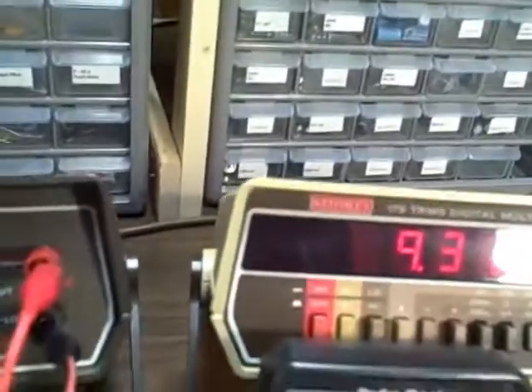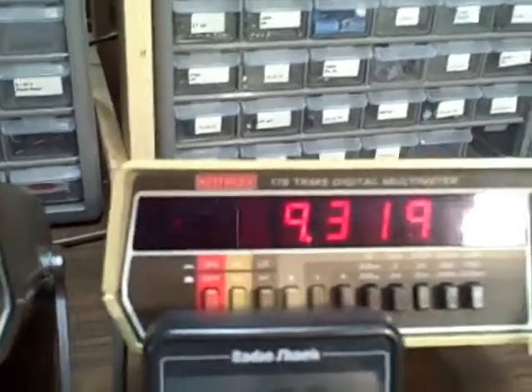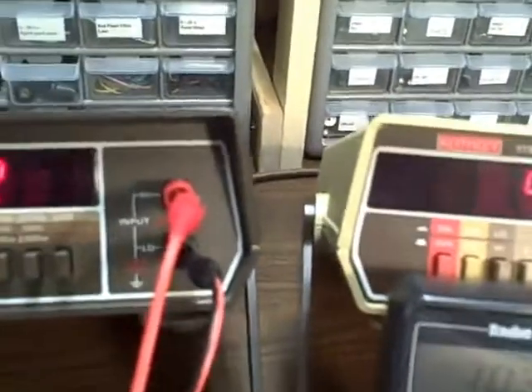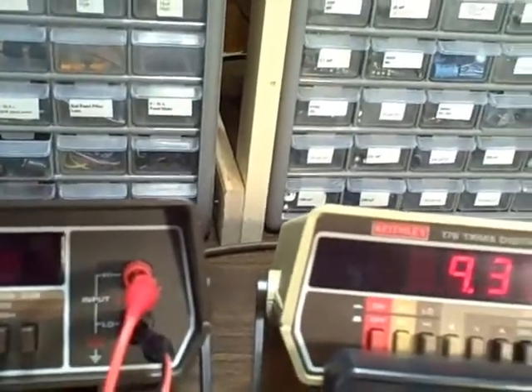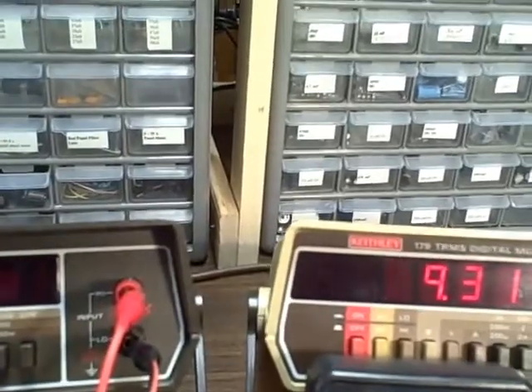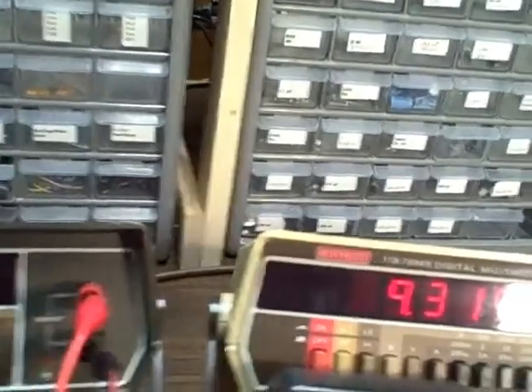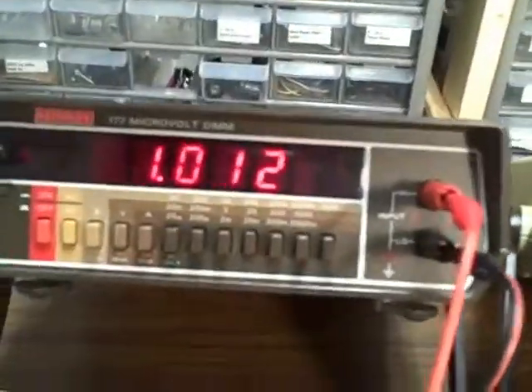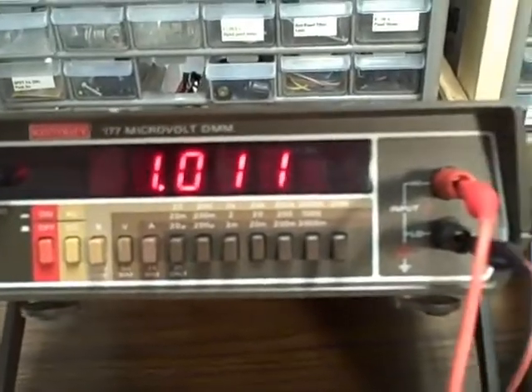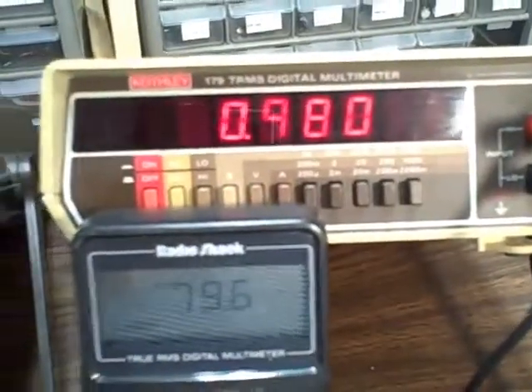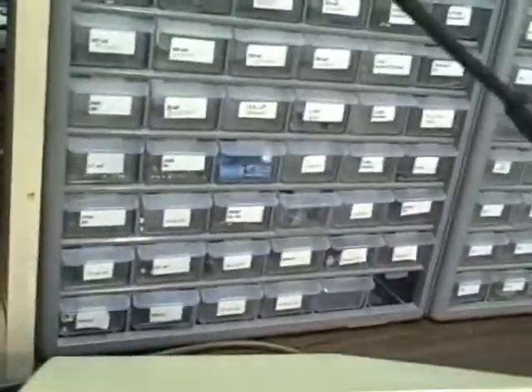But at any rate, the two Keithleys are within a third of a volt at this voltage level, and it is 10 times higher in range than it's actually meant to do. I'm going to go ahead and turn down the voltage. We are reading 1.012 on the 177 and 0.980 on the 179.